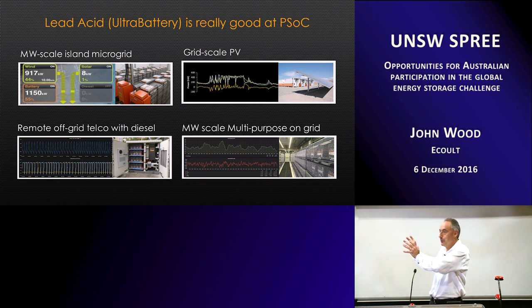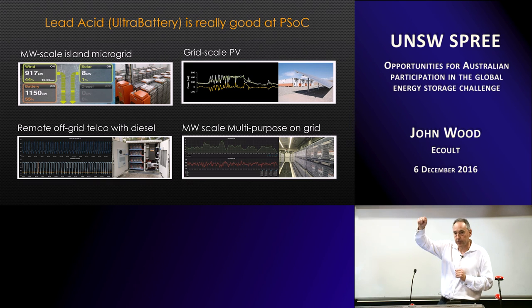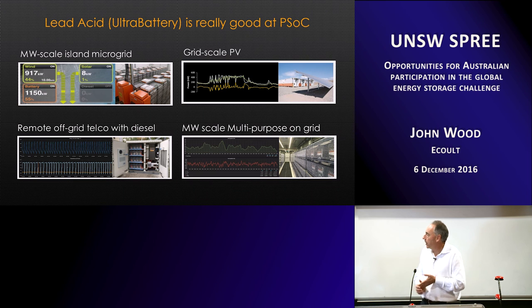And what we did was we went to a remote site, and that site ran on diesel. It had a little bit of solar. And on that site, we put the UltraBatteries. We put them in a fairly tough application. So there's no environmental conditioning for those batteries. They're just sitting in a shelter outside. And all they do is they charge off the diesel at the diesel's most efficient charging rate. Then they discharge for 4 to 6 hours, and they repeat. And that site's been going for more than 2 years now, I think around 2.5 years.